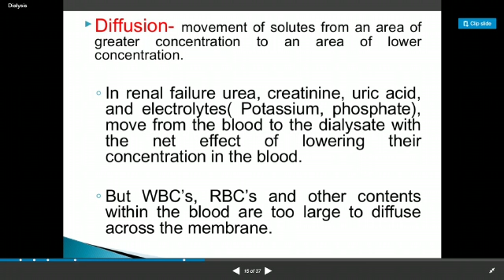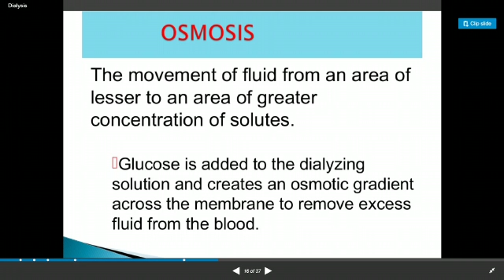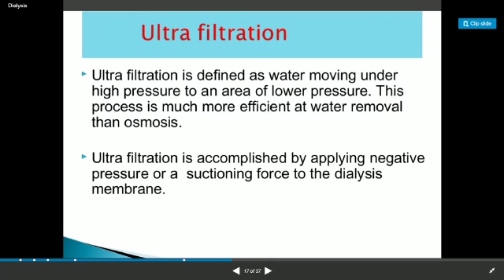Now, by the process of osmosis, the movement of the fluid from an area of the lesser to an area of greater concentration of the solutes, glucose is added to the dialyzing solution and creates an osmotic gradient across the membrane to remove the excess fluid from the blood. Now, the third principle on which the dialyzer is working is the ultrafiltration. Ultrafiltration is defined as the water moving under the high pressure to an area of the lower pressure. This process is much more efficient at water removal than osmosis. So, ultrafiltration is accomplished by applying the negative pressure or a suctioning force to the dialysis membrane.